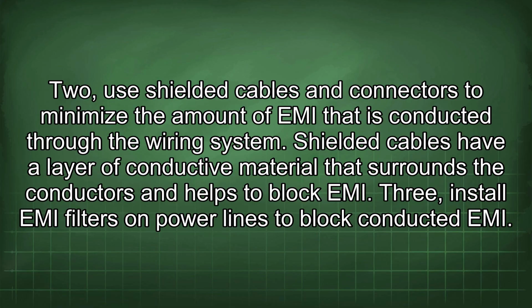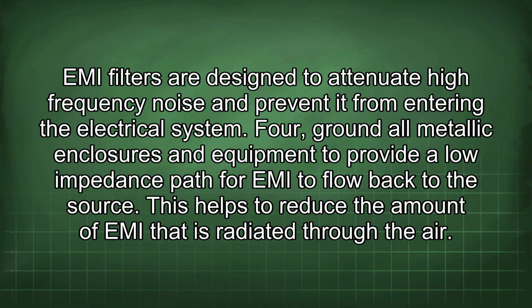3. Install EMI filters on power lines to block conducted EMI. EMI filters are designed to attenuate high-frequency noise and prevent it from entering the electrical system. 4. Ground all metallic enclosures and equipment to provide a low-impedance path for EMI to flow back to the source. This helps to reduce the amount of EMI that is radiated through the air.